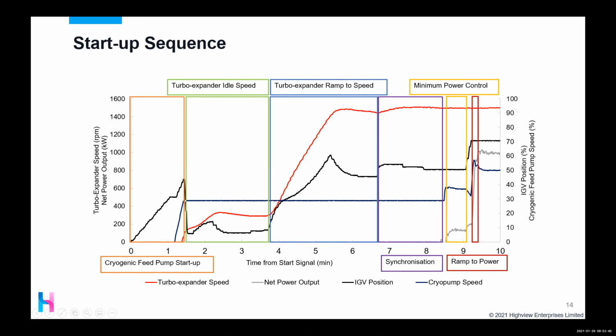And then you ramp up the cryopump to a minimum flow set point. The variable inlet guide vanes close, and they're then controlling to ramp up the speed of the turbine to about 300 RPM. Now we had to remain in this idle speed here. This was a protocol of GE's control system, and this is something that we've since worked with OEMs to remove from subsequent plants. But this is basically their protocol stated that you had to sit at a nominal speed of about 300 RPM for a certain amount of time. And then once you got the AOK from the control system, you could move on to the next phase, which is the speed ramp to nominal RPM.